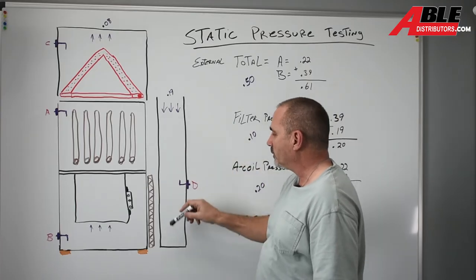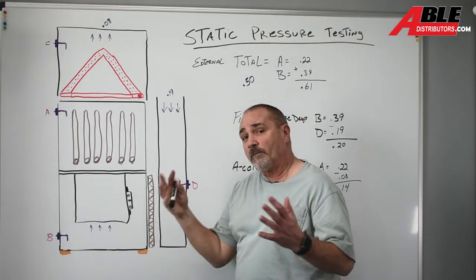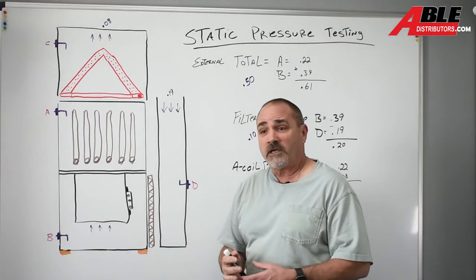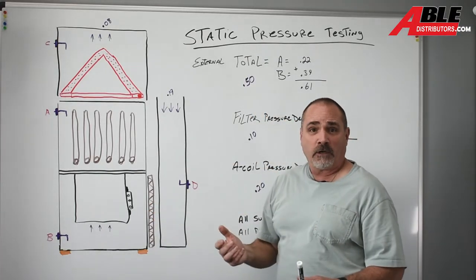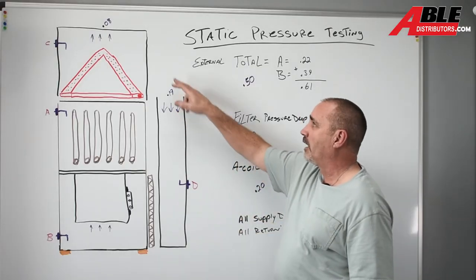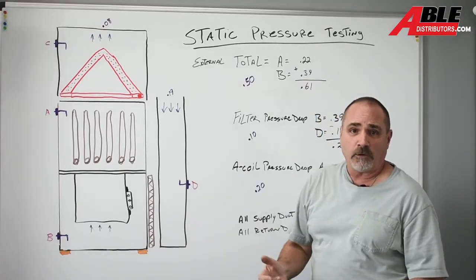So if we were to take that filter and go with a bigger filter or maybe a fiberglass filter, we'd probably drop that in half. And if we added one more return duct, we'd probably get that back down to match the 0.08 and then we'd be good.